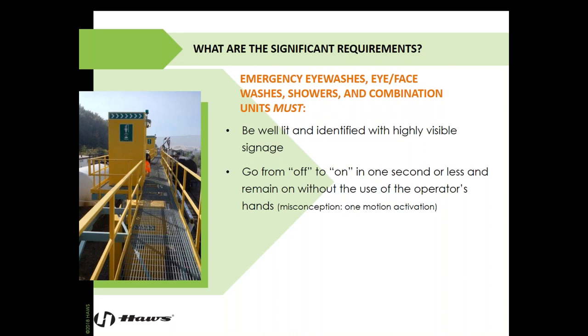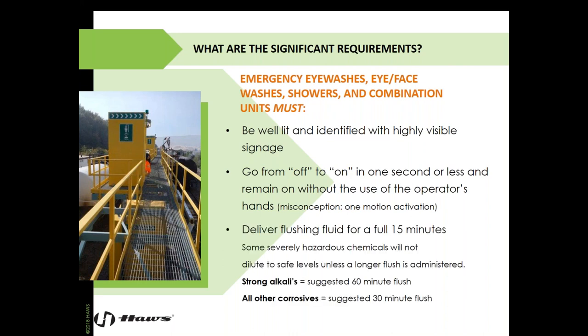And going back to the operator's hands, this is really important because self-closing valves used to be a really prevalent type of valve that was used on emergency equipment. What you would have to do is constantly hold the shower open, constantly hold the eye face wash open. And this can be really difficult to do. You have other emergencies to deal with, removing your clothing, holding your eyes open, and any other emergencies that might arise. So a stay open valve is what's required on this equipment now.